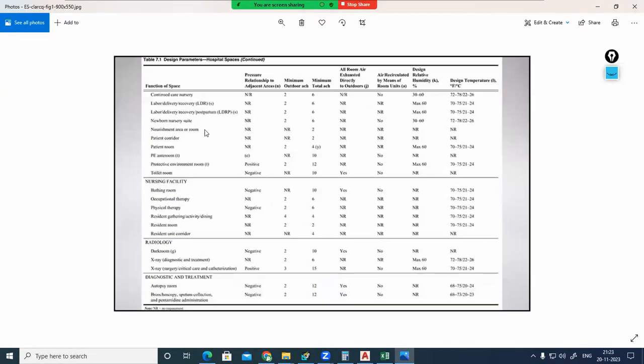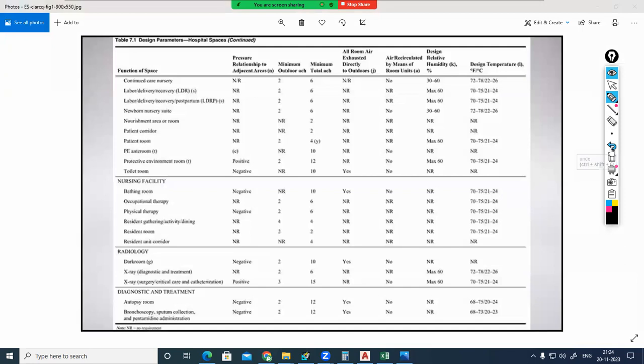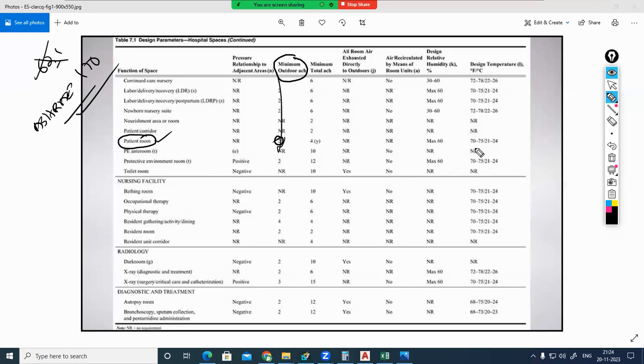Good. Here you can see this is the 170 standard. Here you can see healthcare facilities like patient rooms and all. This is an ASHRAE standard, but not the 62.1 standard. This is 170, and 170 is only for healthcare facilities. Patient rooms, minimum outdoor air changes per hour, how much is it? 2, correct. So from here you can find it, and the conditions might be different. The design temperature in degrees Celsius is like 21 to 24 degrees Celsius in a patient room, and the maximum relative humidity will be 60. So that criteria has to be maintained here. So when you are doing this for a healthcare facility, the standard might be different.